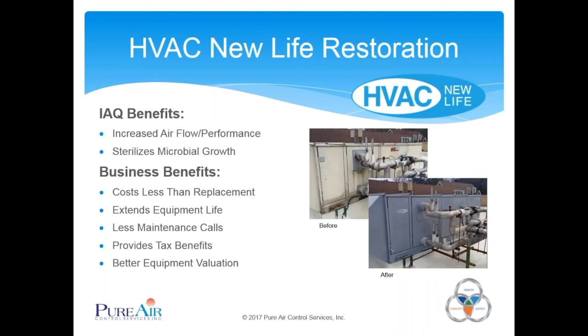Was that you showing me a picture, or was it our estimator? I can't remember - yeah, it was Tanner. They were bringing in a replacement coil that had gone bad, couldn't help it any longer, it was old. They didn't want to do the whole unit, but the new coil couldn't even fit through the two doors to get into the mechanical room and into the air handling unit. So they had to actually buy two separate coils and join them up on the inside of the air handling unit. So sometimes with these mechanical rooms, replacement isn't an option, or it would be tremendously more expensive than just restoring.